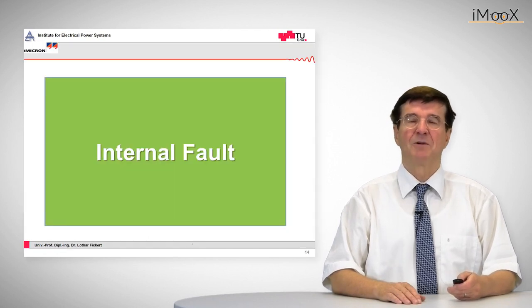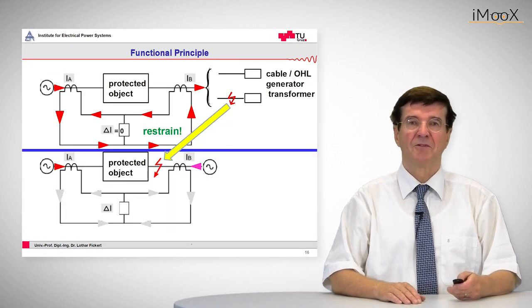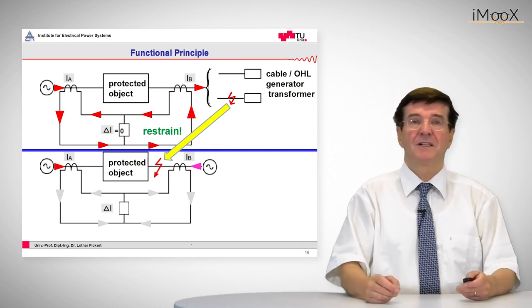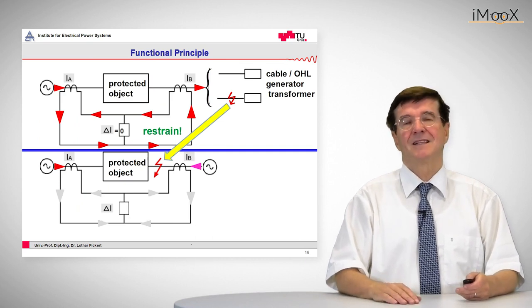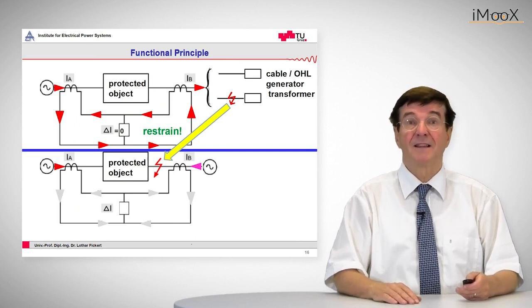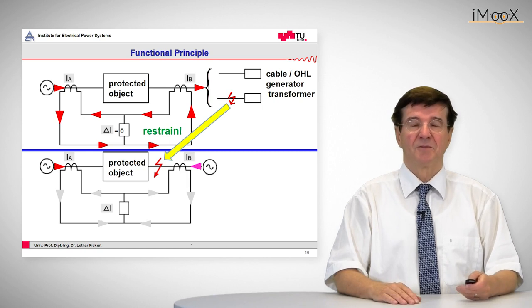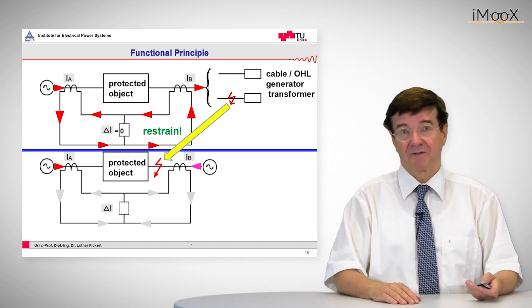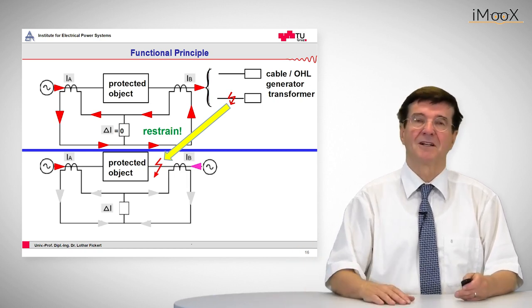A big difference is when we have an internal fault. So in case of an internal fault, the faulty point has moved into the protected area. And now let's see about the currents and their polarity. So from the left side we have the current from source A. On the right side we have the current from source B.